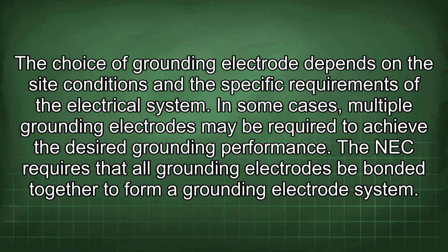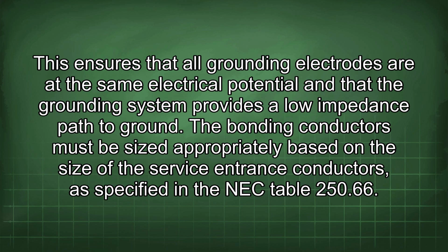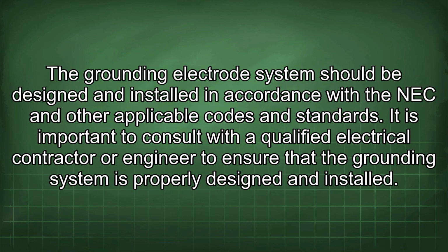The choice of grounding electrode depends on the site conditions and the specific requirements of the electrical system. In some cases, multiple grounding electrodes may be required to achieve the desired grounding performance. The NEC requires that all grounding electrodes be bonded together to form a grounding electrode system. This ensures that all grounding electrodes are at the same electrical potential and that the grounding system provides a low impedance path to ground. The bonding conductors must be sized appropriately based on the size of the service entrance conductors, as specified in the NEC Table 250.66. The grounding electrode system should be designed and installed in accordance with the NEC and other applicable codes and standards.